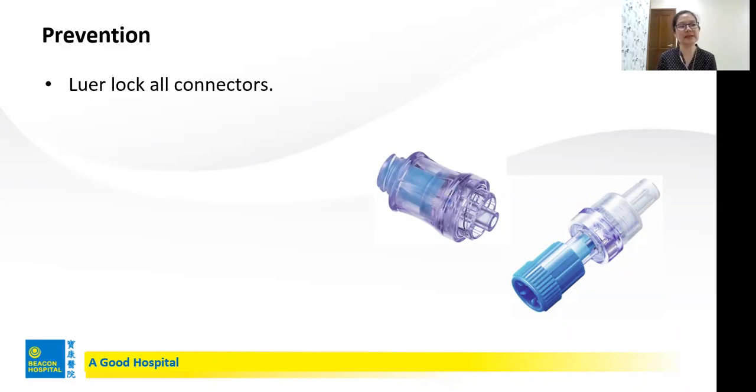Some infusion sets are slip-head, okay? They slip into your catheter. Some are Luer lock, okay? So please, the preferred type is to choose the Luer lock. Infusion set, catheter, syringe, stopper, please choose Luer lock connector. This will be more secure.